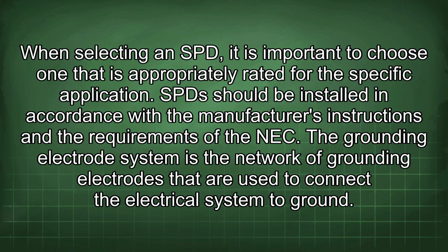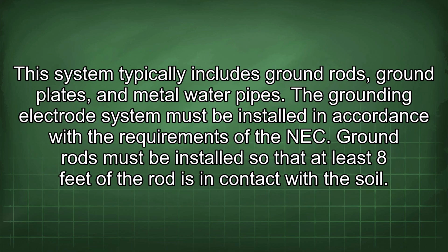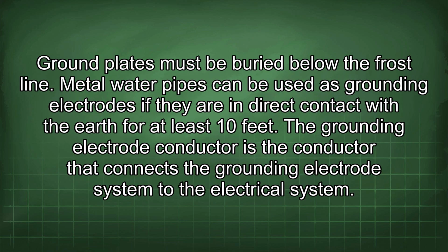The grounding electrode system is the network of grounding electrodes that are used to connect the electrical system to ground. This system typically includes ground rods, ground plates, and metal water pipes. The grounding electrode system must be installed in accordance with the requirements of the NEC. Ground rods must be installed so that at least 8 feet of the rod is in contact with the soil. Ground plates must be buried below the frost line.